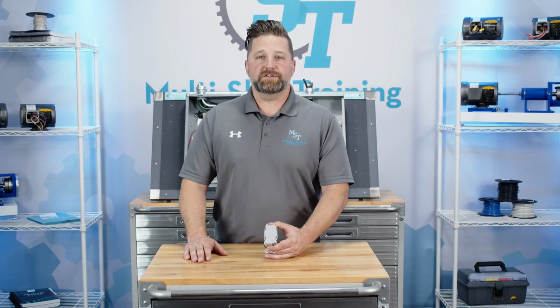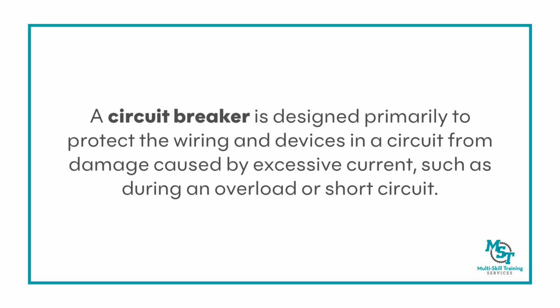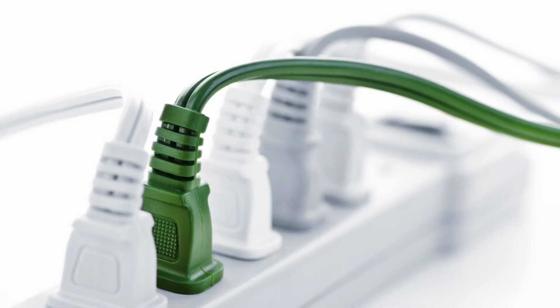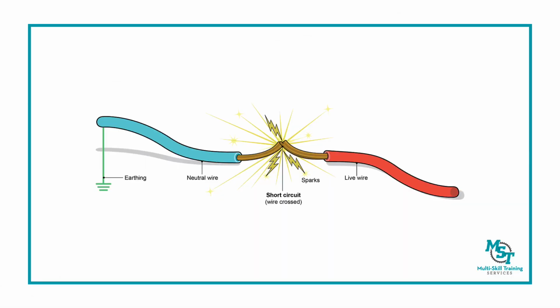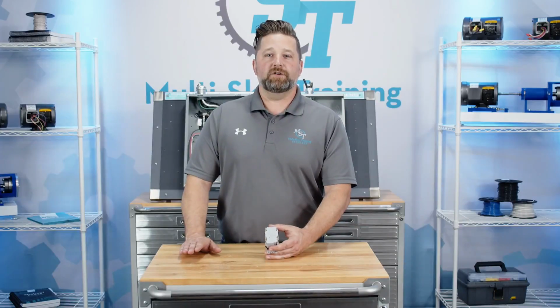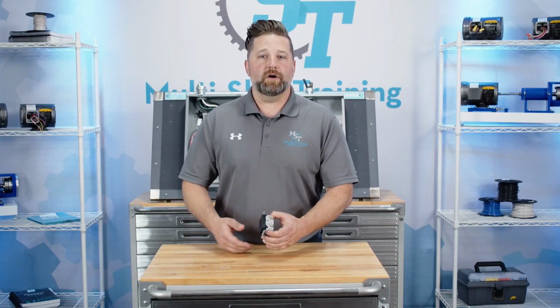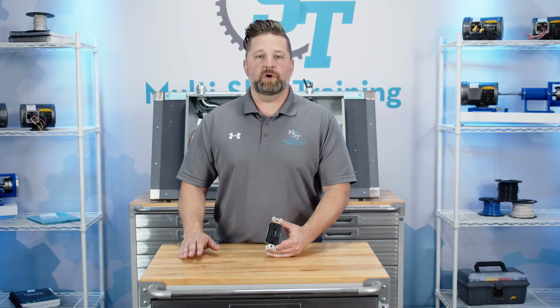While both circuit breakers and GFCIs play important roles in electrical safety, they serve distinct purposes. A circuit breaker is designed primarily to protect the wiring and devices in a circuit from damage caused by excessive current, such as during an overload or short circuit. Remember, an overload occurs when too many devices are operating on the same circuit, drawing more current than the wiring is rated to handle. A short circuit occurs when a hot wire directly contacts a neutral or ground wire, creating a sudden surge of current. In either case, the breaker trips to cut off the power and prevent overheating, fires, or equipment damage.